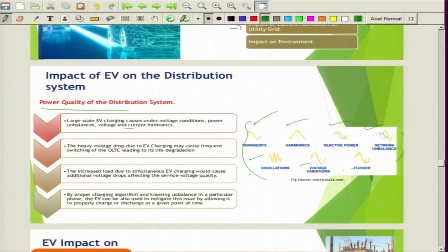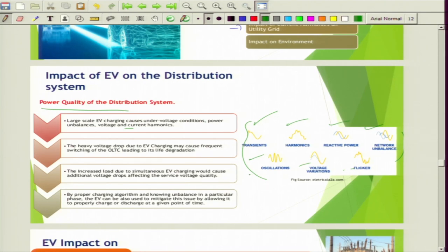If different vehicles are doing single-phase charging and connected to different phases, there could be variation in current carried by different phases. An under-voltage scenario may be seen because if multiple electric vehicles are plugged in and being charged from the point of common coupling, the voltage may drop down. And because converters are present, harmonics are injected as well — these are the important power quality issues that arise when electric vehicles are present in the distribution system.